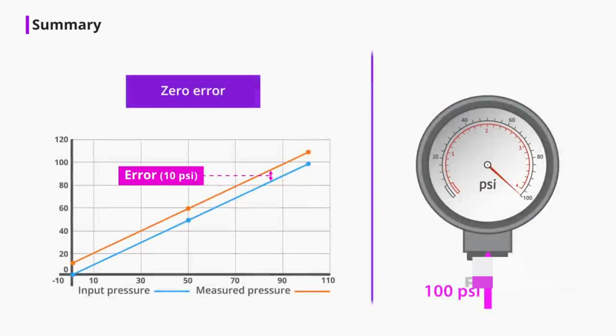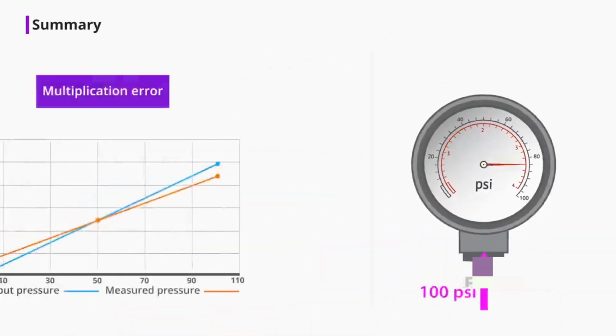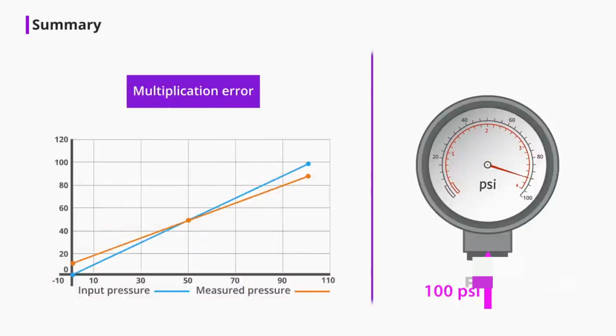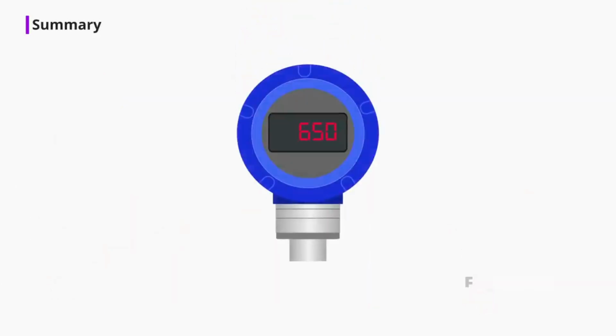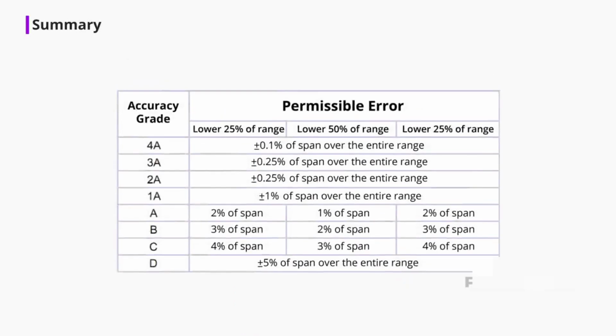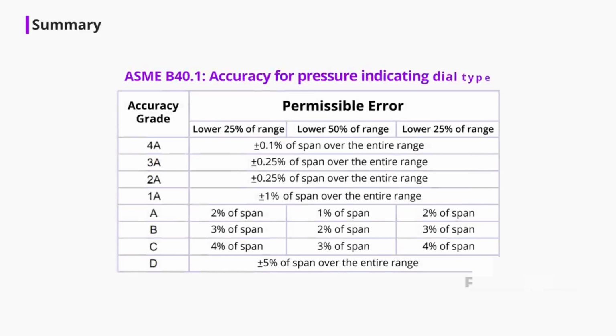Zero error is the error of the same amount and in the same direction throughout the entire pressure range, regardless of the input pressure. Multiplication error is the error when the total movement of the mechanism does not equal the total change in input. Many pressure gauges are equipped with a pressure transducer that converts pressure into an electrical signal used to operate a digital display. The American Society of Mechanical Engineers ASME B40.1 standard defines the accuracy grades of dial-type gauges. For mechanical pressure gauges, accuracy is usually defined as a percentage of the entire span of the range.